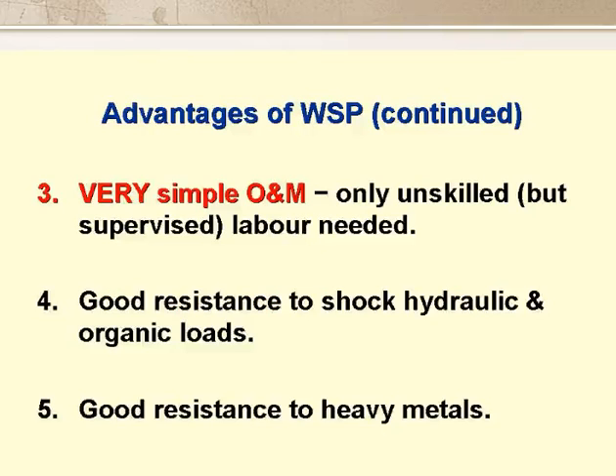Ponds are very simple to operate and maintain, and only unskilled but supervised labour is needed. Because of their large size, they have a very good resistance to shock loads, both hydraulic and organic. And they have excellent resistance to heavy metals, up to at least a mixed heavy metal content of 30 mg per litre.